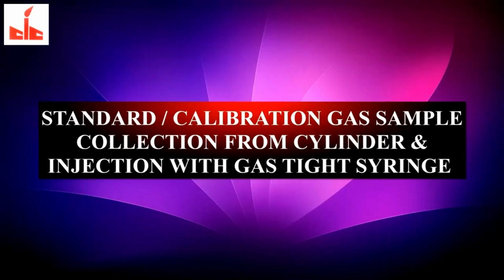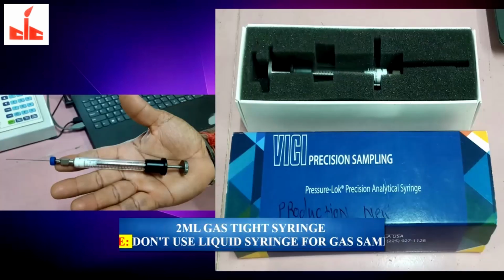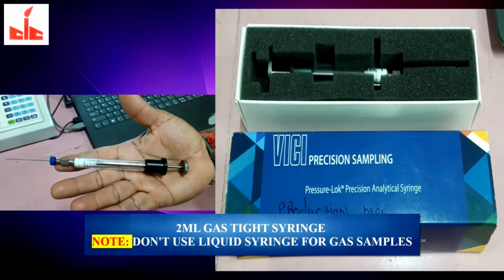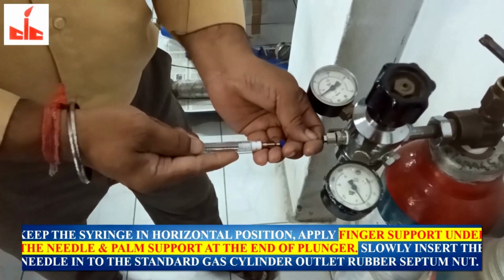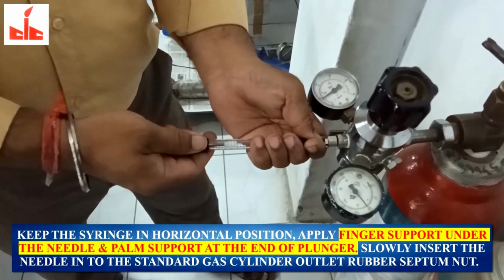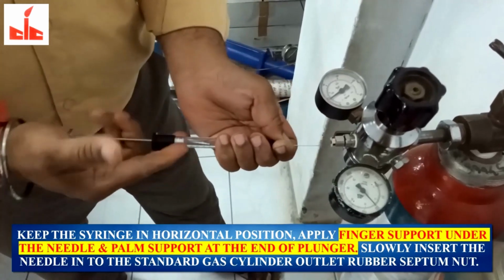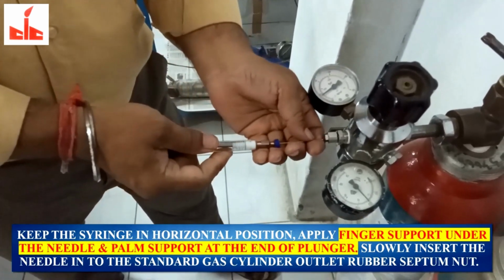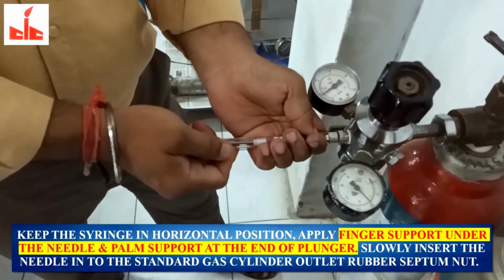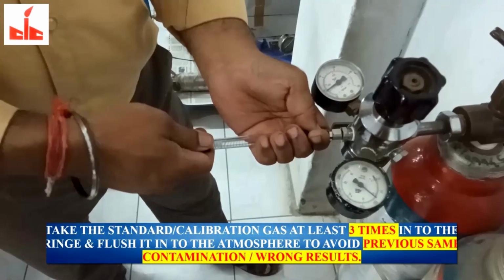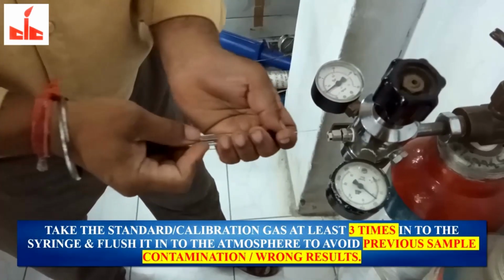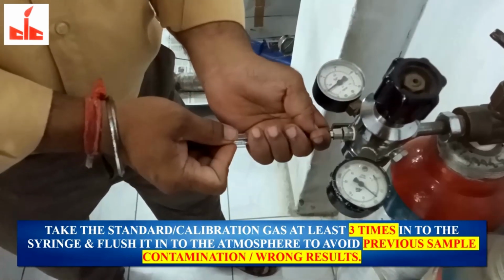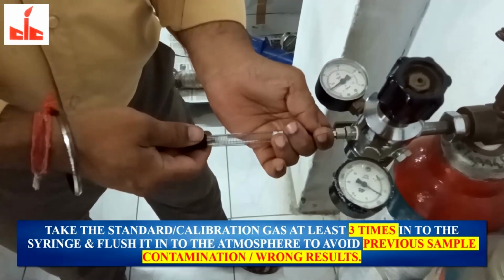Standard or calibration gas sample collection from the cylinder, and injection with a gas-tight syringe in the injector. Here we are using a 2 ml gas-tight syringe to collect the gas. Don't use a liquid syringe for gas samples. Keep the syringe in horizontal position, apply finger support under the needle, and palm support at the end of the plunger. Slowly insert the needle into the standard gas cylinder outlet rubber septum nut. Take the standard or calibration gas at least 3 times into the syringe and flush it into the atmosphere to avoid previous sample contamination or wrong results.